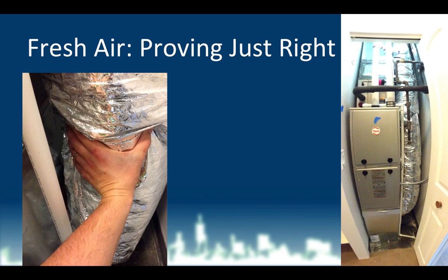So what I'm going to do is, first of all, molest this duct. I feel it up, and I could spend potentially 5 minutes feeling up this duct. I feel like a total perv while I'm doing this. Hopefully nobody's watching me, but I need to find out where exactly in here the person who installed this damper put it, because the guy who installed it does not understand why he is installing it. He doesn't understand that somebody else is going to come along and have to find this thing and have to set it to the right amount.